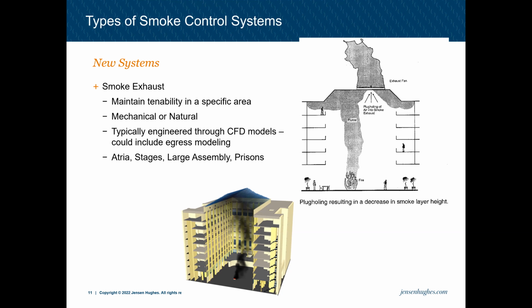And the types of these smoke exhaust systems are usually required for high risk spaces that usually have a lot of people and other factors that make fires especially dangerous. Some of these areas are atria, stages, large assembly, and prisons. So atrium, in section 404 of the IBC, any atrium that connects 3 or more stories requires a smoke control system.